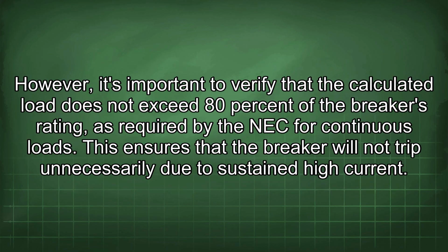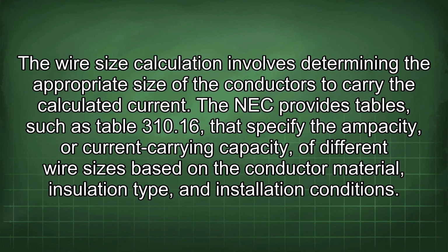However, it's important to verify that the calculated load does not exceed 80% of the breaker's rating, as required by the NEC for continuous loads. This ensures that the breaker will not trip unnecessarily due to sustained high current. The wire size calculation involves determining the appropriate size of the conductors to carry the calculated current. The NEC provides tables, such as Table 310.16, that specify the ampacity or current carrying capacity of different wire sizes based on the conductor material, insulation type, and installation conditions.